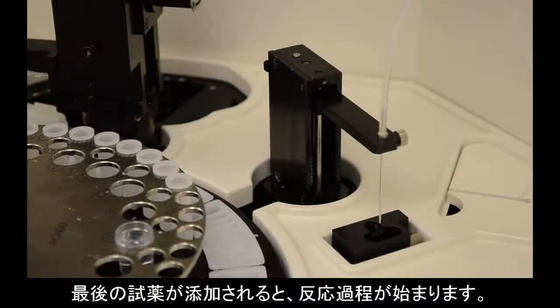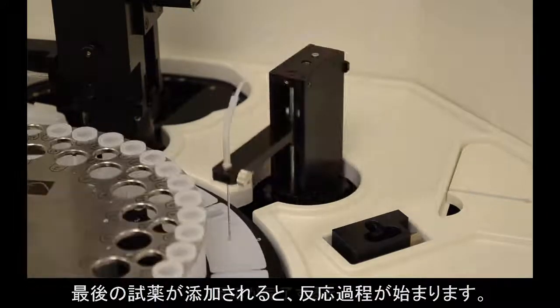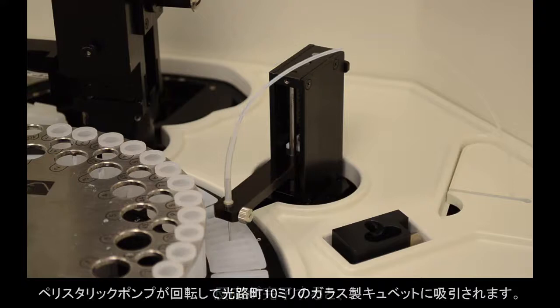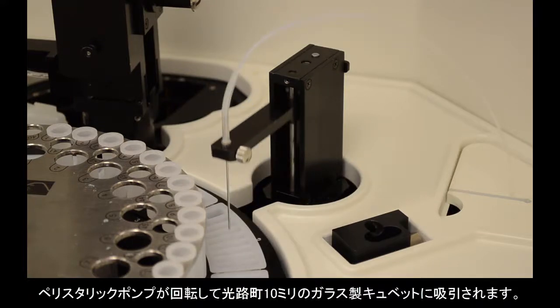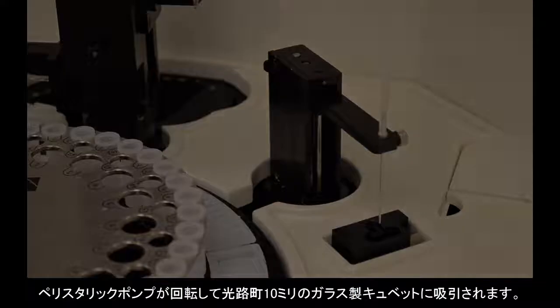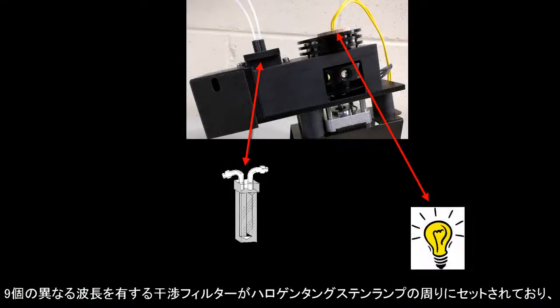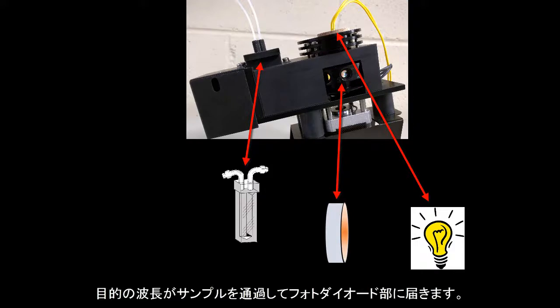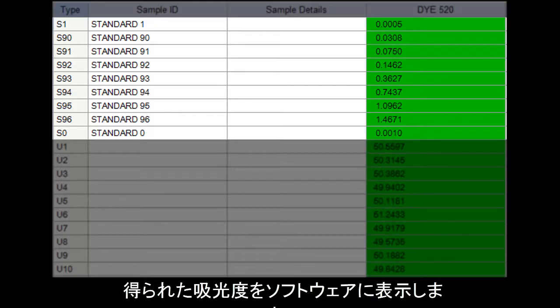Once the final reagent has been added, an incubation period begins. When the reaction has been allowed to come to completion, a peristaltic pump moves the sample to the 10 millimeter optical glass cuvette. The tungsten halogen lamp is surrounded by a filter wheel which contains 9 different wavelength filters. The correct filter spins in front of the lamp and light from the lamp shines through the filter, through the sample, and hits the photodiode board. The absorbance is then calculated and displayed in the software. After the reading, the peristaltic pump spins again, pulling the reaction liquid to the waste container.